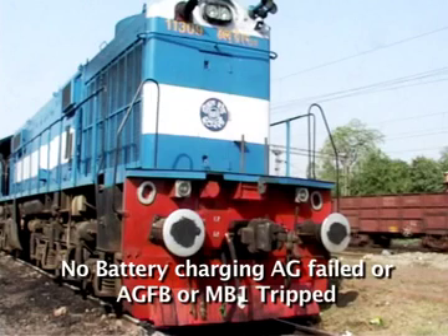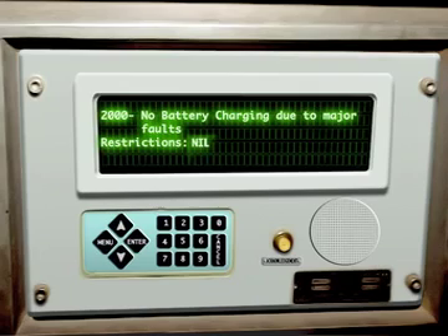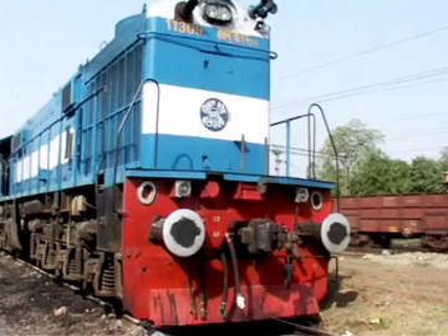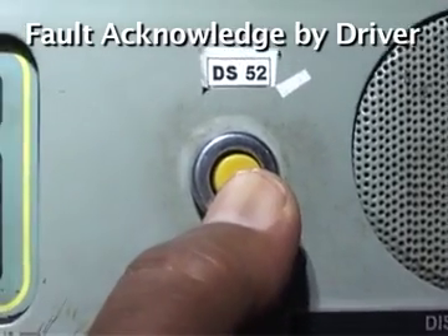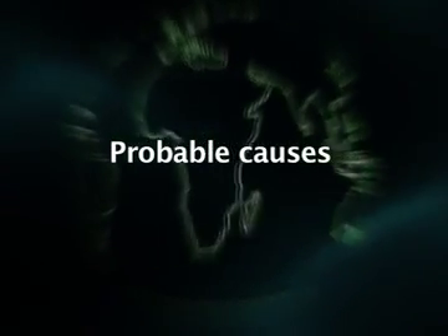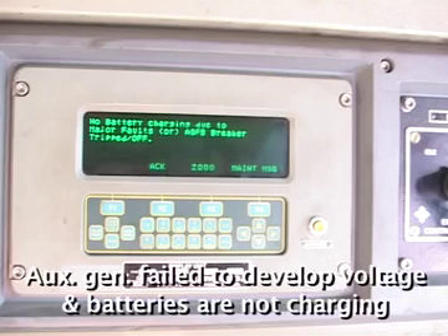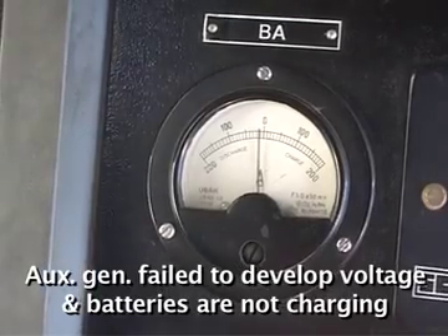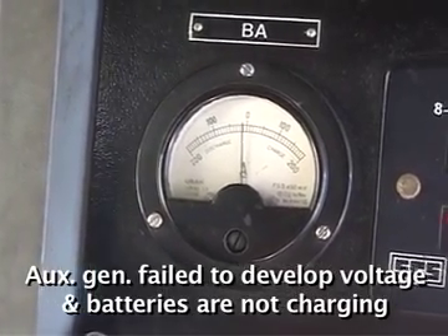No battery charging, AG failed or AGFB or MB1 tripped. Fault message coming. No battery charging due to major faults. Message code 2000. Restriction nil. Alarm bell, buzzer for 30 seconds for every 10 minutes. Driver acknowledging fault. Probable cause: auxiliary generator failed to develop voltage and batteries are not charging.